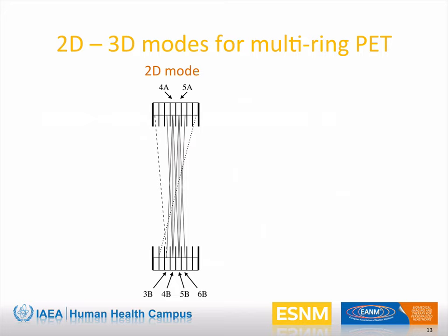In this way, data coming from a single slice of object or patient are recorded by 1-2 rings only. This simplification makes image reconstruction process easier. In addition, in order to limit the number of single events reaching a single detector, each ring is physically separated from the adjacent one with a septum made of high-Z material. For example, the dotted LOR is blocked by the septum between block 2B and 3B.